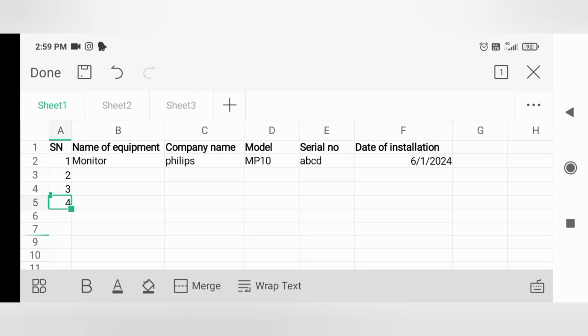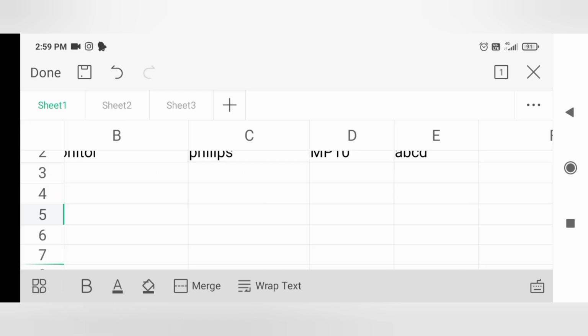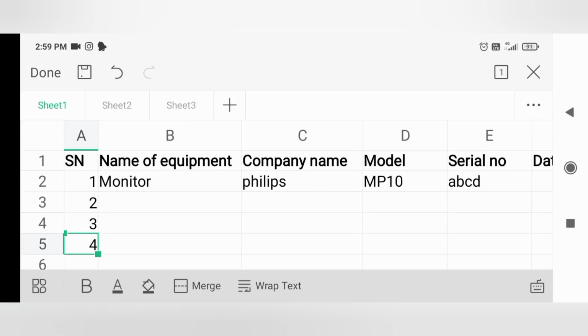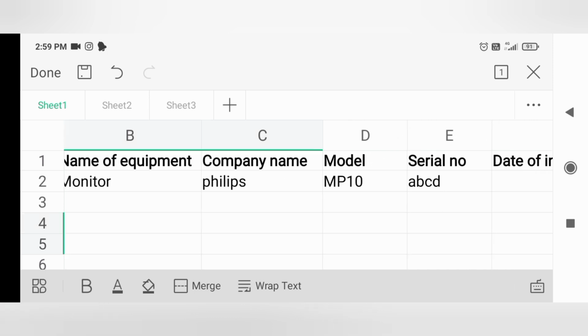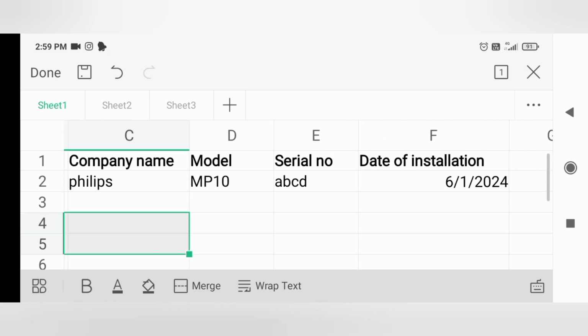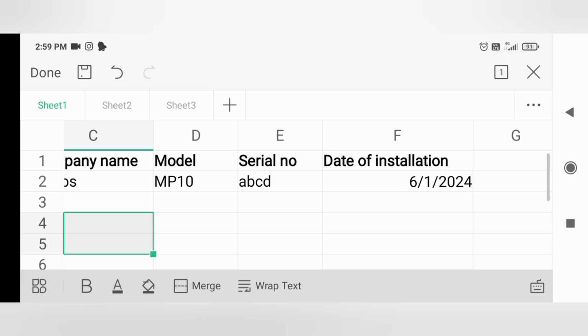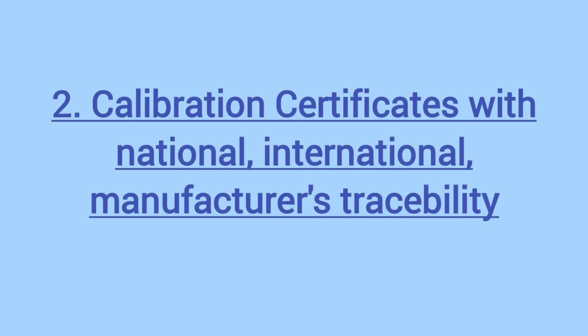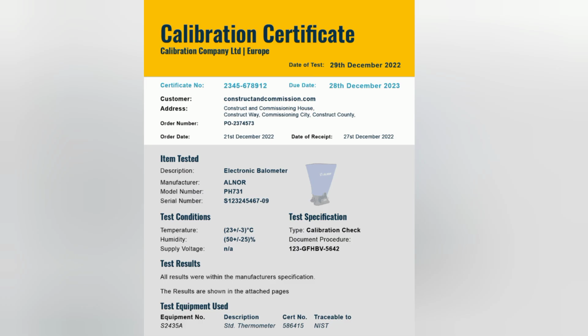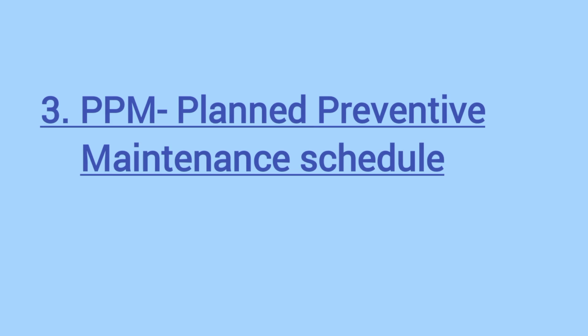So the very first is the asset list of medical electronic equipment. This file includes the list of each and every medical equipment in the hospital or organization that you are working in. This list comprises the name of the equipment, company name, model name, serial number of the equipment and date of installation. The second file is calibration certificates with national or international manufacturer traceability. This file includes calibration certificates from the installation time of the equipment as well as certificates of calibration on a regular basis. The third file is the PPM schedule.